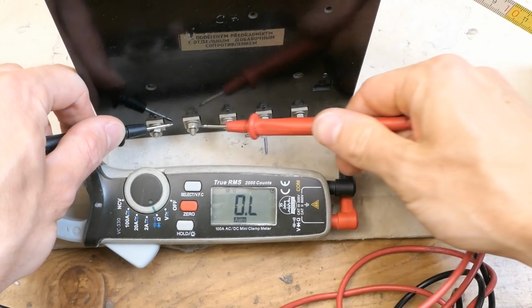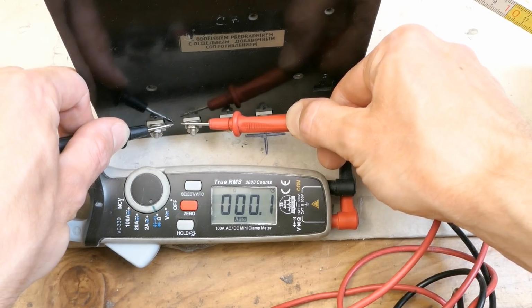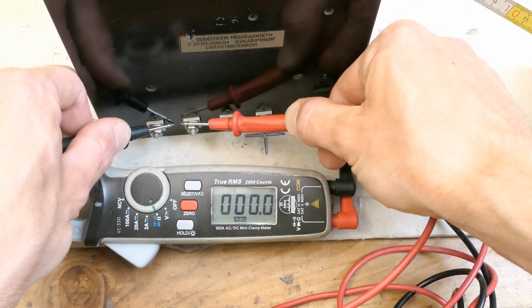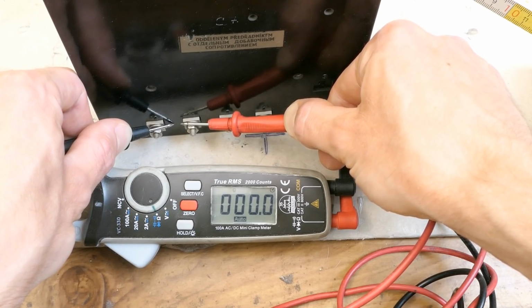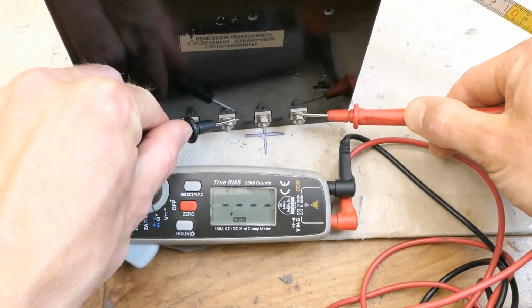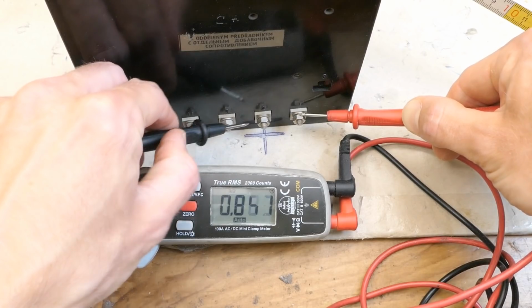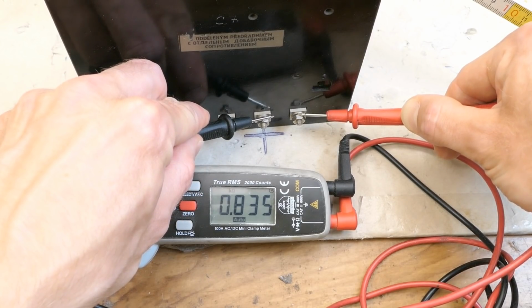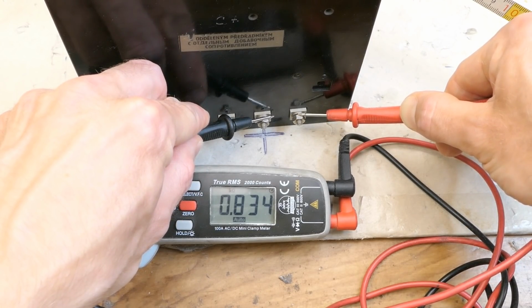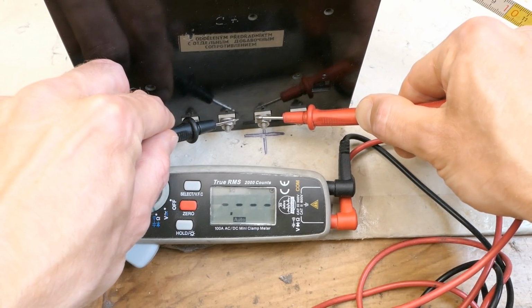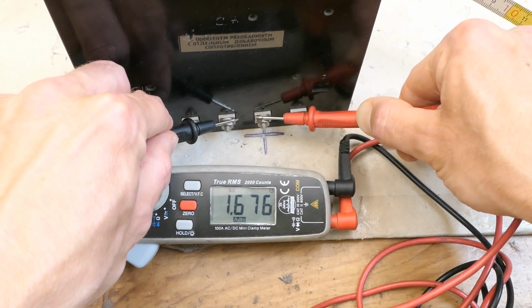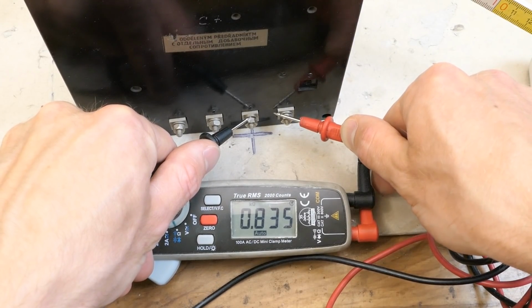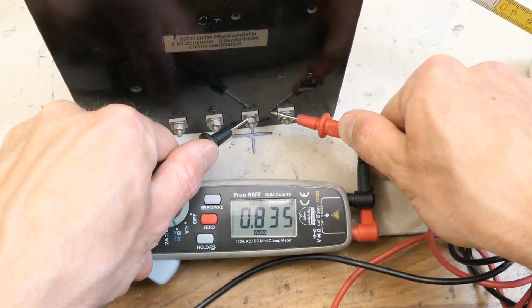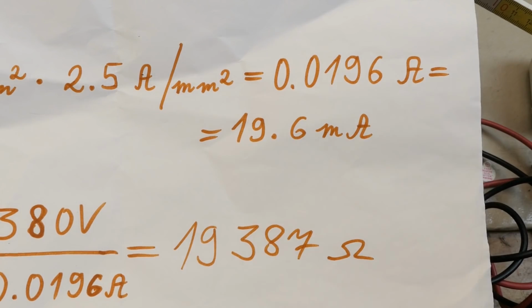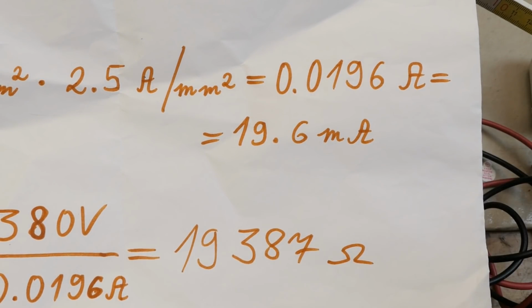Let's try to measure the resistances of the coils. Well, this is probably the primary of the current sensing transformer, which is a very low resistance. And here should be the voltage coils, 840 ohms, 840 ohms roughly again for the other coils, and this is just showing them in a series. So the resistance of the voltage coils is lower here, which would also suggest a higher current necessary. But of course the current could be lower. Maybe they were using a lower current density in the wire.